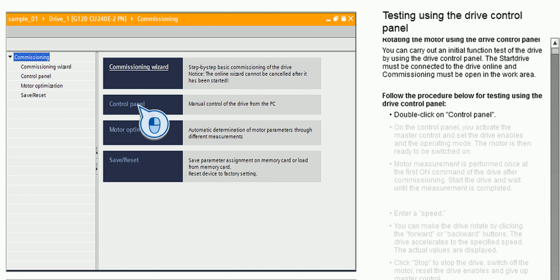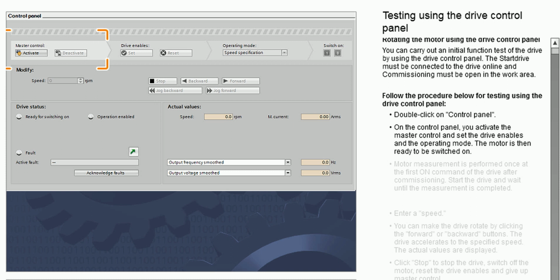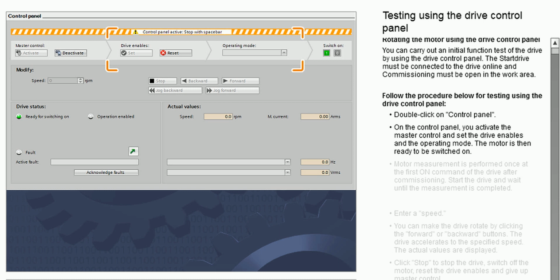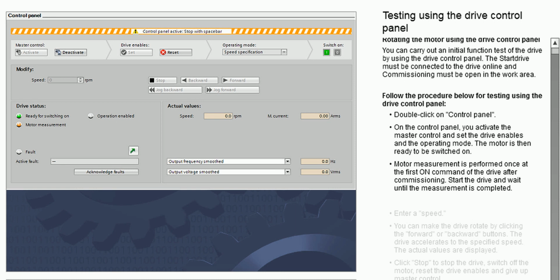Double-click on Control Panel. On the control panel, you activate the master control and set the drive enables and the operating mode. The motor is then ready to be switched on. Motor measurement is performed once at the first on command of the drive after commissioning. Start the drive and wait until the measurement is completed.